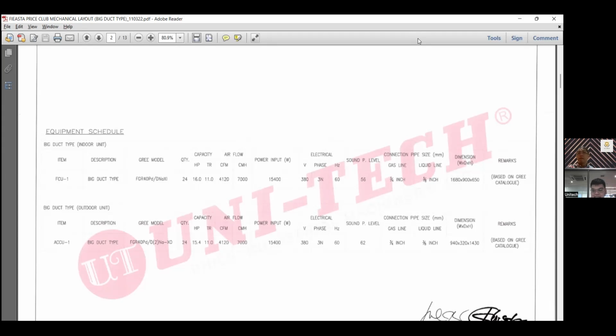During the design process, these are the equipment we selected: the FCU1 big duct type, 24 quantities at 11 TR. The selection is based on, number one, availability and the application for the system, since the fabric duct is good and more economical.